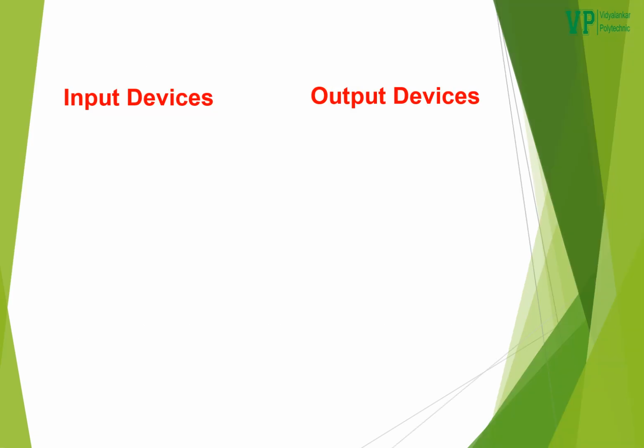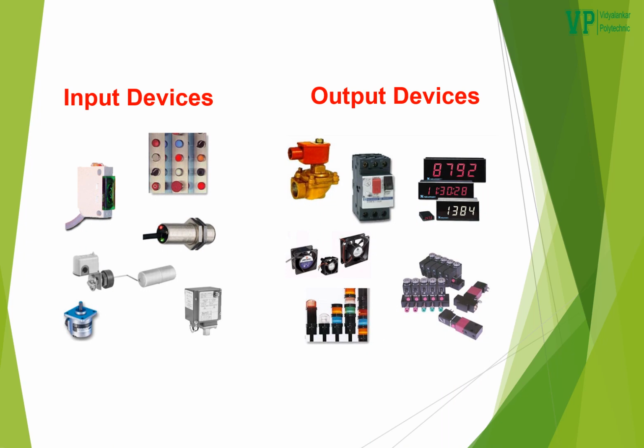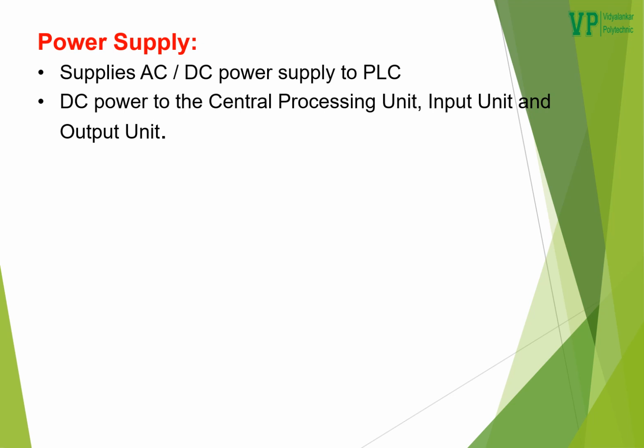Here are a few examples for input and output devices. Under input devices, we can see there are toggle switches, push button switches, proximity switches, limit switches. Under output devices, we can see solenoid valves, fans, alarms, lamps, and contactors. Also, digital displays. Power supply supplies AC or DC power supply to PLC, DC power to the central processing unit, input unit, and output unit. Basically, it has an integrated SMPS which takes care of the lower operating voltages inside the PLC.